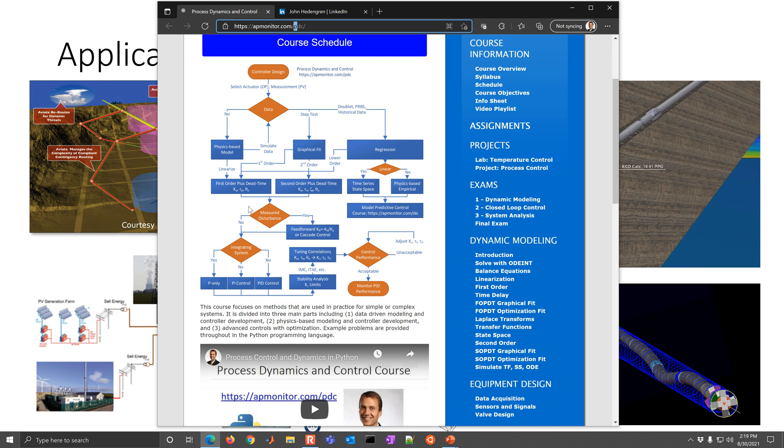And then the second part is going to be the controller design. So we have a measured disturbance. If we have a measured disturbance, we can design a feedforward or cascade controller to reject that disturbance. And if we don't, then we'll design a PID controller. And if we have an integrating system, then we'll use a P-only controller. Or if it's not an integrating system, then a PI or PID controller.